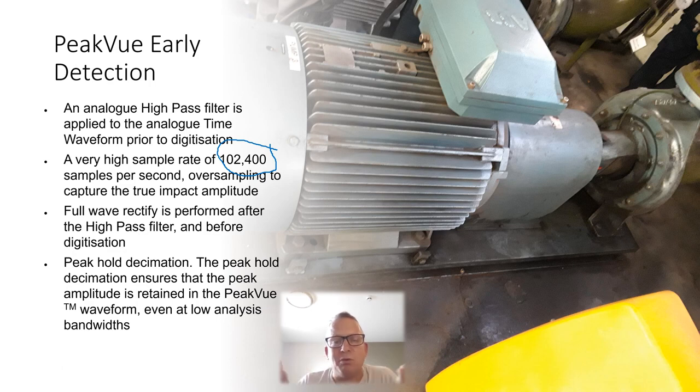Very short pulse, short duration, really high frequency. They're sampling really fast to capture it. Then they rectify it, digitize it, peak hold decimation, which by the name PeakVue comes from, where it holds a peak value and ensures the peak value is retained and it gives you some really crisp, clear data.